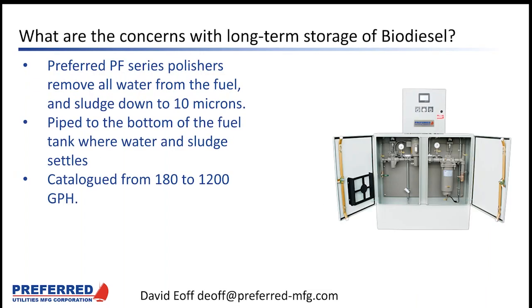Preferred series of PF polishers remove all water from the fuel, and they filter the sludge down to 10 microns. Actually, our standard filter element is 10 microns. You can replace it with any size filtration element you want, or whatever your gensets require.